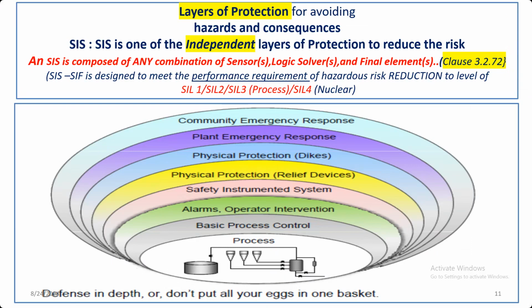So the focus is going to be SIS, which is composed of any combination of sensors, logic solvers and final elements. You can have 2 sensors, 2 logic solvers, 2 final elements, or 3 sensors, 3 logic solvers, 3 final elements, depending upon what level of SIL is required to be established. Now, let me clarify here that the process industry standard defines only up to SIL 3. SIL 4 is not applicable for the process industries. It is applicable to the nuclear industry or maybe other industries.